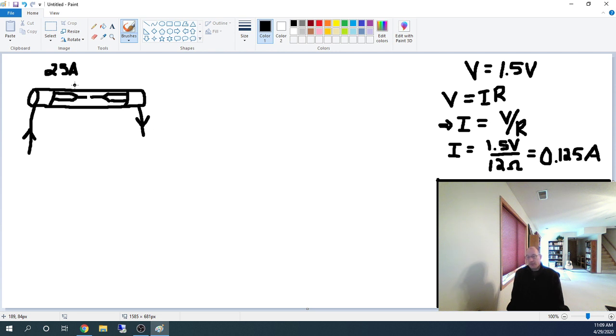People didn't understand what was going on electrically with fusing. They'd say stuff like, well, it says 20 amps, not realizing that it was a limiter. They thought maybe the fuse was something like the source, so a 40 amp fuse is way better than a 20 amp fuse. I'm going to use a 40 amp fuse, which means turn on all your devices, no problem, right? The fuse won't blow. But the wire that it's protecting would start a fire.